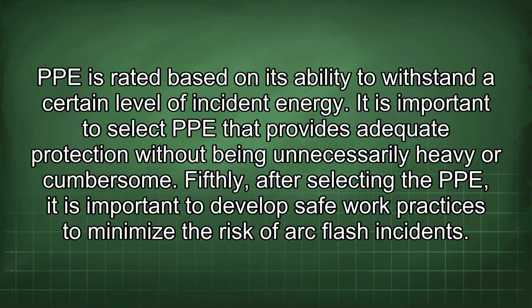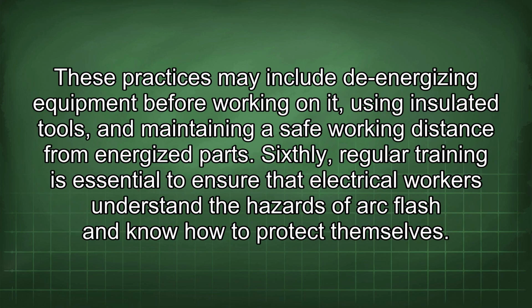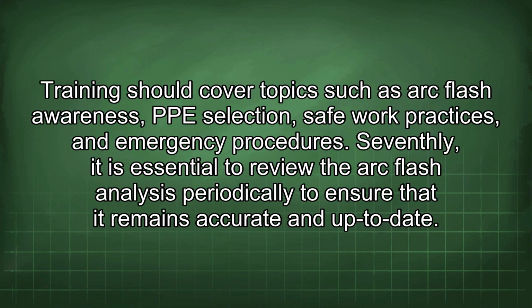PPE is rated based on its ability to withstand a certain level of incident energy. It is important to select PPE that provides adequate protection without being unnecessarily heavy or cumbersome. Fifthly, after selecting the PPE, it is important to develop safe work practices to minimize the risk of arc flash incidents. These practices may include de-energizing equipment before working on it, using insulated tools, and maintaining a safe working distance from energized parts. Sixthly, regular training is essential to ensure that electrical workers understand the hazards of arc flash and know how to protect themselves. Training should cover topics such as arc flash awareness, PPE selection, safe work practices, and emergency procedures.